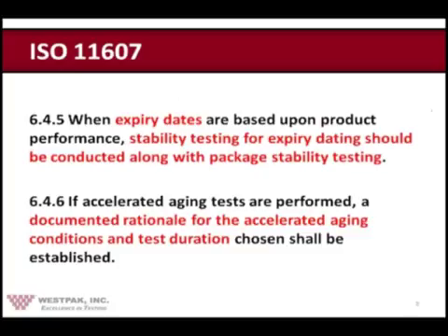You could, I suppose, claim just the package integrity testing and test the package alone, but we rarely see that actually happen. Note that the accelerated aging may be conducted at a number of different temperature conditions based on the response of the materials in the product and package to the effects of temperature.